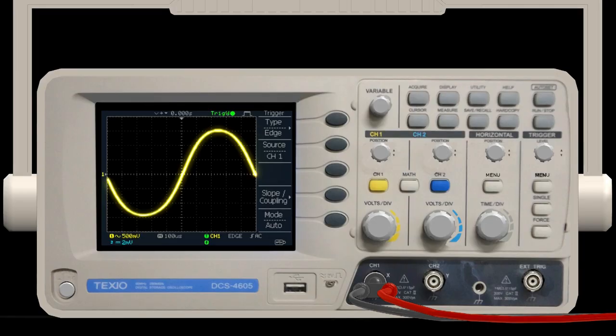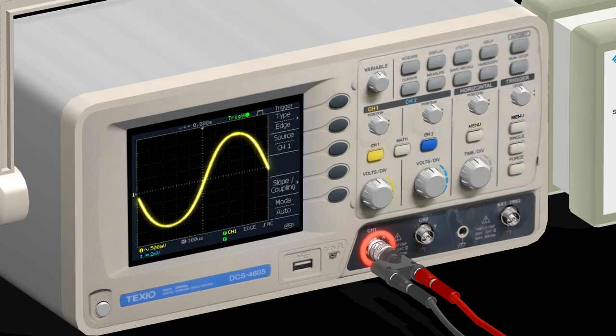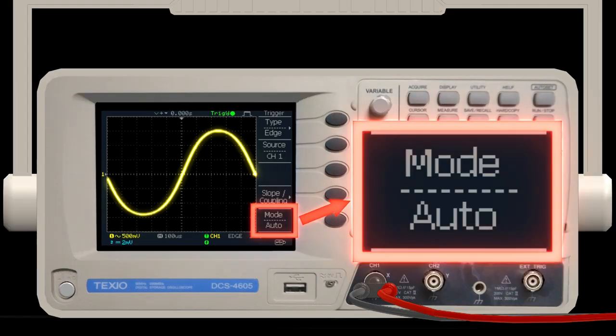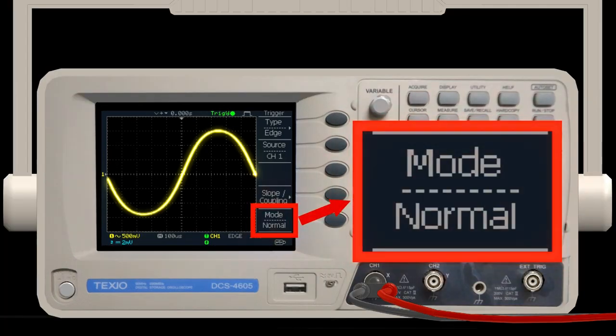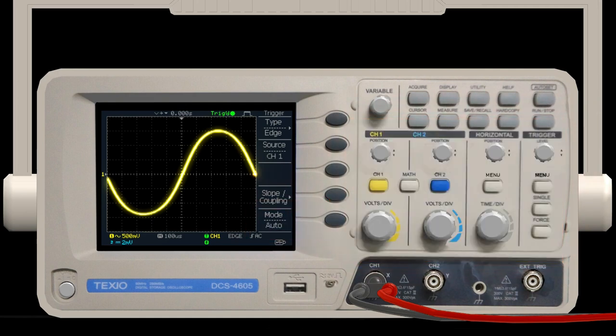For detailed trigger settings, press this menu button. Set the source of the signal you want to observe to channel 1 or channel 2. Set the mode to auto or normal. Use the trigger level knob to adjust the threshold. For clarity, the red line indicates the trigger level.